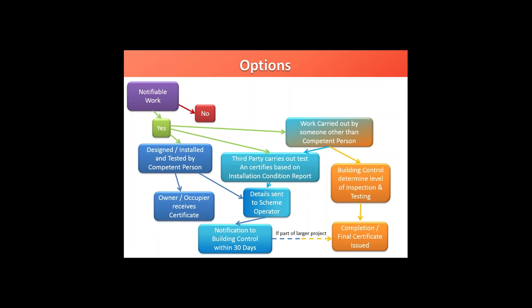The person carrying out the work sends details to a scheme operator — they have to be signed up to an accreditation scheme which assesses their competence and maintains records. At the same time, the person carrying out the work gives a certificate to the owner and occupier of the building. Building control becomes aware of this some 30 days later when the scheme operators send through a notification. This works perfectly adequately where the electrical work is the only work being carried out, but if it's part of another project, this 30-day delay can cause difficulty when trying to issue completion or final certificates under building regulations.